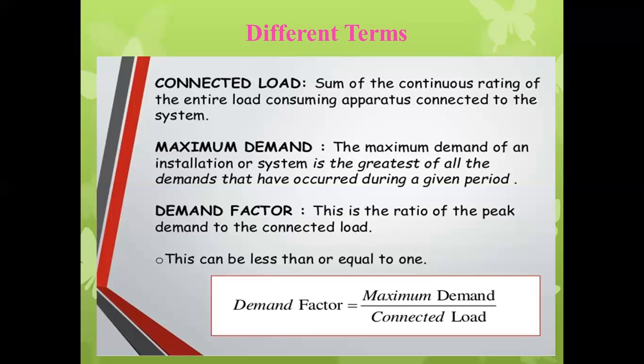So the next term used in the electrical power system is the demand factor. This is the ratio of the peak demand to the connected load. As we know, the demand factor is the ratio of maximum demand to connected load for the given time period. Connected load is greater than the maximum demand, that's why the demand factor is always less than 1. We can find the percentage demand factor by multiplying by 100. Maximum demand is the maximum load for the particular time period, but connected load is the sum of the continuous rating of all the equipment. So that's why connected load is greater than the maximum demand, and the demand factor is always less than 1.